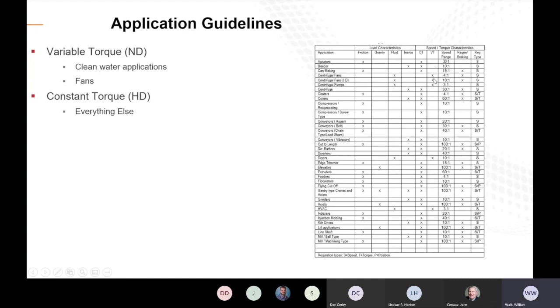But if you take the small list of variable torque applications, I'll have to remember to pull up the reference. This is from an engineering handbook. All of our variable torque applications: fans and pumps, dryers, another type of fan, HVAC, also another type of fan. So it's pretty easy whenever it comes to determining the needs of your application and how you should specify your VFD. So again, anything that's going to be variable torque or normal duty, that'll be your clean water applications and your fans. And for your constant torque or heavy duty applications, that'll be everything else.